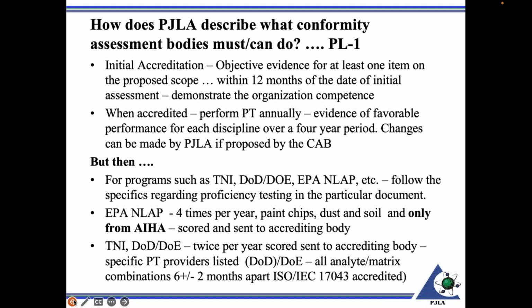Now, what's acceptable? Right off the bat, we'll talk about this a little bit later too in more detail, certainly a third-party program, whether it's accredited or not. Of course, it could be totally disreputable too. If it's totally disreputable, then that's another thing. Or an inter-laboratory comparison, and those would be acceptable, but it should be something within 12 months of the date of the initial assessment. Can't be something you did 2 years ago, 3 years ago. It has to be within the 12 months before the start of the assessment, or at least roughly the start of the assessment. You're off a little bit.